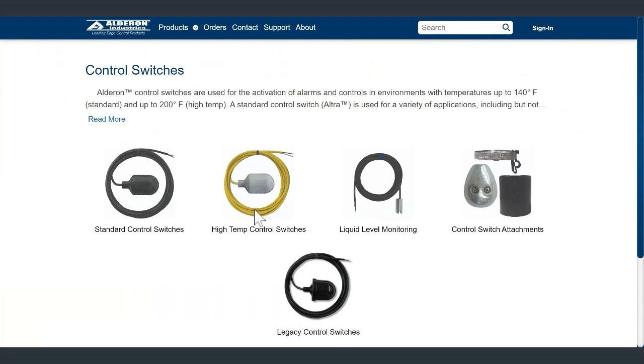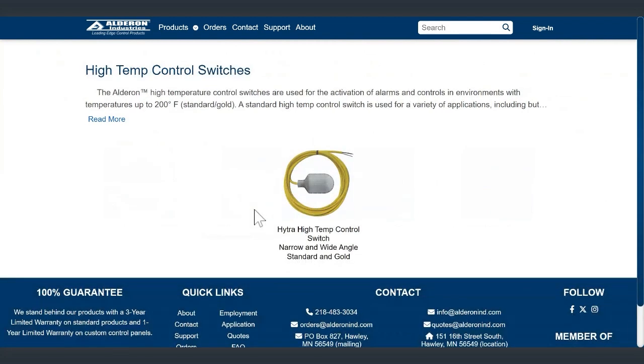And then we also have high temp control switch. So the high temp is denoted by the yellow cable here. We have tested this in boiling water and in our oven up to like 350, 400 degrees, and it still tests out good. We tested next to competitors, and in the oven, the competitors is melting. But even in boiling waters, ours works. We can only rate it to 212 degrees because that's what the cable's rated for. But I can tell you it does work in higher temperatures than that.